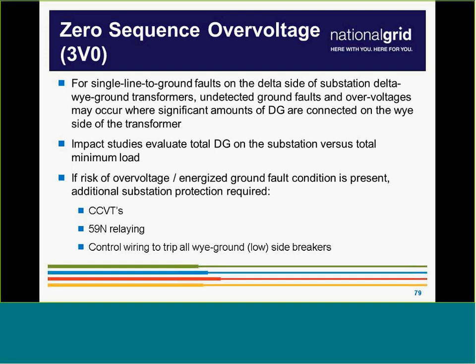The remote ends will trip because they're designed to trip for faults on the transmission system. Then what happens is your distributed generation shifts the neutral out of that transformer up. It's also energizing the ground fault, and it's raising that potential on the entire line. As the distributed generation is sourcing that, it looks just like load for the distribution system. All the DGs think, I'm serving load. It's a fault, and they just can't tell. So that's why we install 3V0.